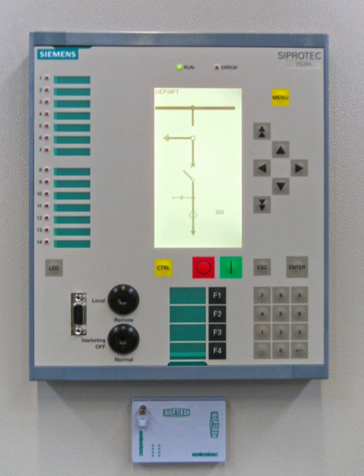Topic: Components. Protection systems usually comprise five components: current and voltage transformers to step down the high voltages and currents of the electrical power system to convenient levels for the relays to deal with, protective relays to sense the fault and initiate a trip, or disconnection, order, circuit breakers to open, close the system based on relay and autorecloser commands, batteries to provide power in case of power disconnection in the system, communication channels to allow analysis of current and voltage at remote terminals of a line and to allow remote tripping of equipment.